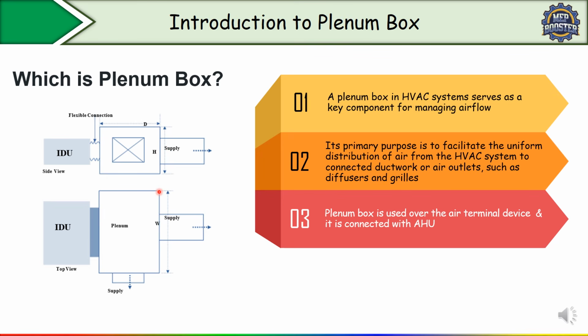Basically, the plenum box is used to convert turbulent flow to laminar flow. In this way we can reduce the noise. It also provides a transition zone that helps maintain consistent pressure across the outlet. So this is essential for maintaining the design airflow rate. Is it clear?